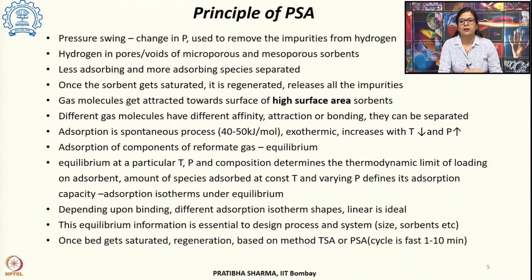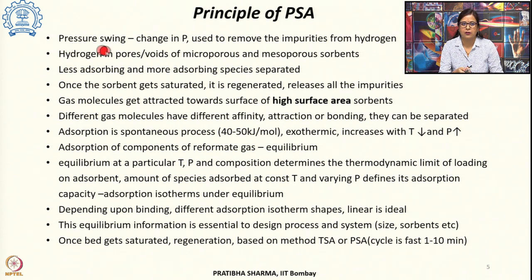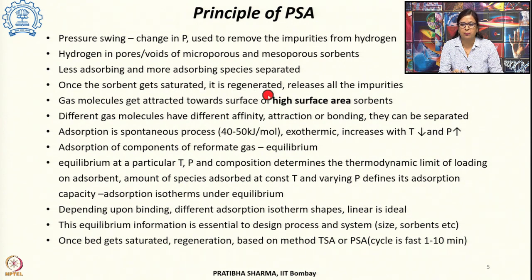Once the adsorbents get saturated with the impurities or contaminants, they need to be regenerated, which is done by the change in pressure. Pressure swing adsorption occurs at a higher pressure, and desorption occurs at a lower pressure. Once the sorbent gets saturated, it has to be regenerated back by reducing the pressure, under which condition it releases all the impurities present in the bed.